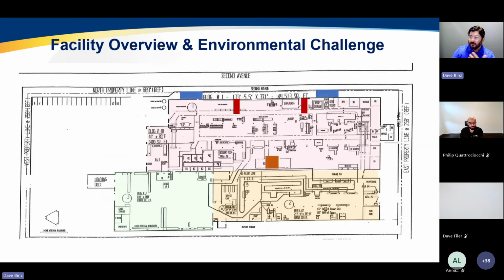And so what we did is that we looked at, how can we still make sure we're meeting your ventilation needs, but providing some temperature relief? If I deployed a traditional comfort control or mechanical cooling, my energy costs would be outrageous because I've got a 400-degree oven, I've got 40,000 CFM of a process exhaust. That's extremely expensive to add a lot of mechanical cooling.